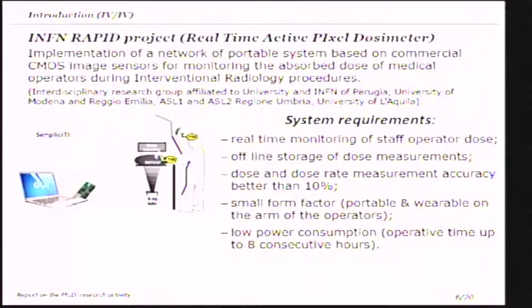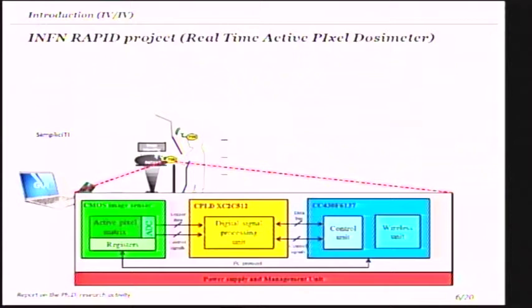Based on a commercial image sensor to monitor in real-time the absorbed dose of the medical operator. The system requirements are: real-time monitoring of the dose, offline storage of dose measurements, accuracy better than 10 percent — which is the actual accuracy of passive dosimeters — portable device, and low power consumption. The dosimeters are worn by the operator on different parts of the body, in particular on the areas most exposed to x-ray radiation.